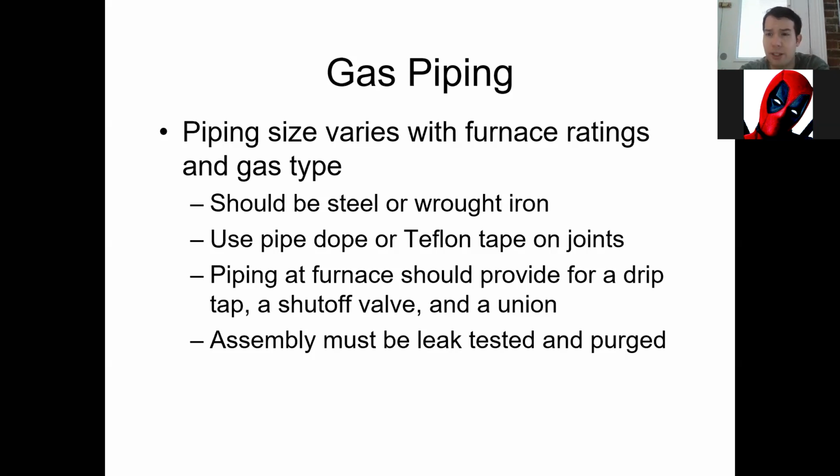Usually that's one of the easiest ways to check for leaks, is you spray down all the connections with a bubble solution. Usually it's like ammonia and a couple other things, but it'll detect. What'll happen is it'll sit there on the connection, and then if there's a leak, it'll blow up. You'll see a bubble just boop and it'll pop, but it'll keep blowing up a bubble. If you ever looked for a leak on a tire with a soap solution, it's the same exact process, same kind of idea.